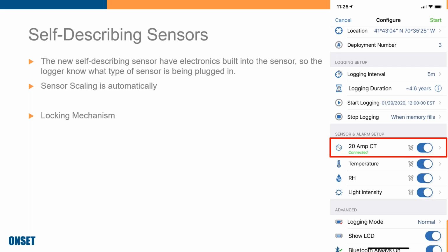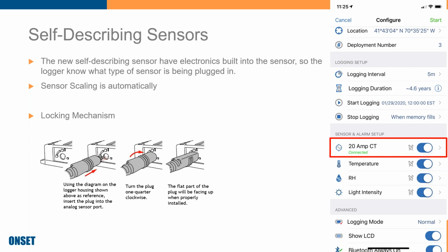Now, one of the other things we added, many of you mentioned concerns that on the older products the jack would sometimes come loose, especially if there was weight on it or you weren't sure it was fully plugged in. So we added a locking mechanism, which also helps keep the IP54 rating. You plug it in at a 45-degree angle and then turn it, and the flat top of the sensor faces up, locking the sensor into place so it won't wiggle out. If you're carrying the logger with 3 or 4 current transformers hanging off it, it's not going to plug out.